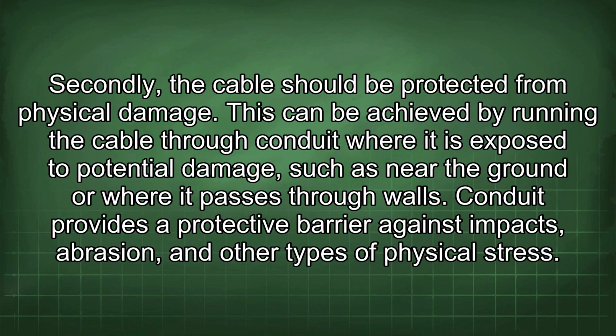Secondly, the cable should be protected from physical damage. This can be achieved by running the cable through conduit where it is exposed to potential damage, such as near the ground or where it passes through walls. Conduit provides a protective barrier against impacts, abrasion, and other types of physical stress.